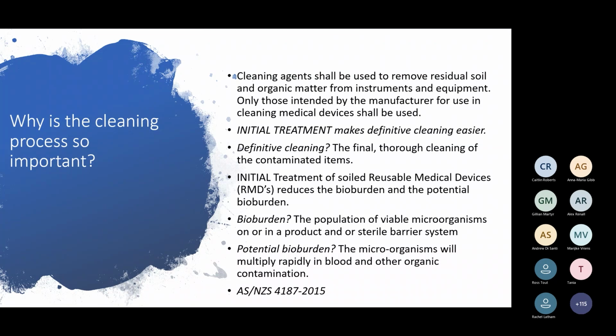Now, initial treatment makes definitive cleaning easier. Definitive cleaning is the final cleaning process that you do before you bag it and put it in the sterilizer. Initial treatment of soiled devices reduces the bioburden and the potential bioburden. So what's bioburden? Bioburden is the population of viable microorganisms on or in a product or sterile barrier system. And the potential bioburden is the amount of microorganisms that can rapidly multiply in blood and other organic contamination. This is why it's really important that we treat instruments at the point of use: clean off blood, clean off pus, whatever is on those instruments, wipe them off initially at the point of use so that you're reducing the potential bioburden that can grow on those instruments. Because if you can get rid of them at the point of use, it makes your cleaning process a lot more effective.